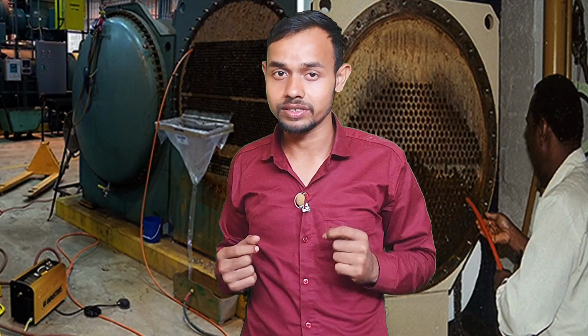Yes. So, explained in an easy way. An HVAC chiller cools water in the chilled water circuits throughout the building, but over time the minerals and the dirt start sticking inside the cooling tubes, forming a hard layer called scale deposit. Yes, calcium, magnesium, silica, dust. So friends, just like a white layer inside a water bottle, a scale build up in geyser coils, white crust inside a kettle. So now imagine the same white crust forming inside your chiller tubes. What is the result?